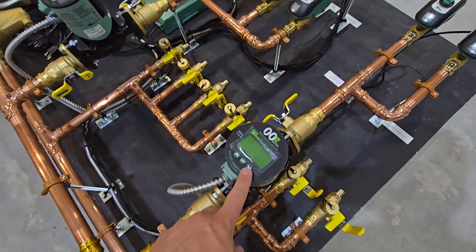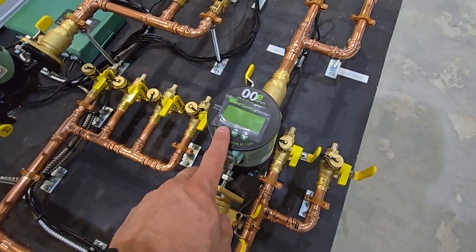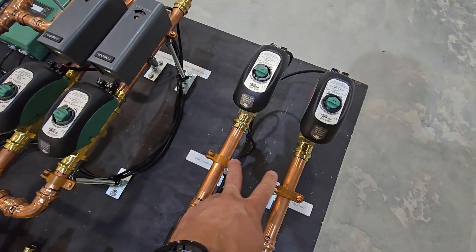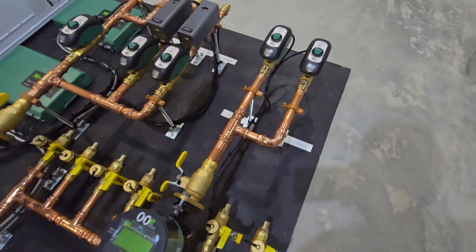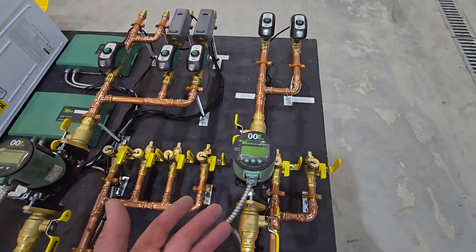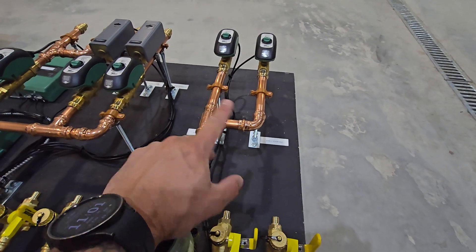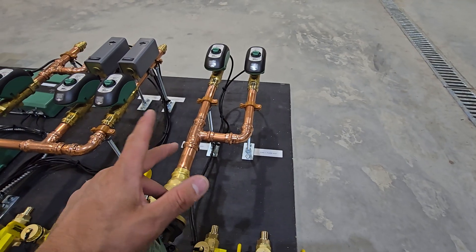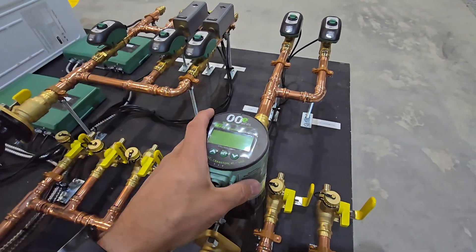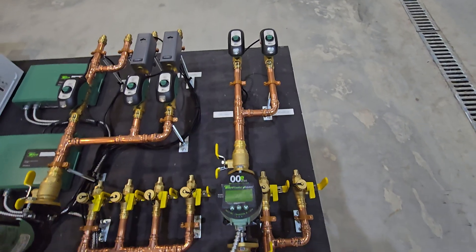You can see there's a single variable speed circulator — a Taco 00e series, specifically the VT 2218 variable speed delta T circ — and that's feeding two zone valves that split to two manifolds. You might wonder why there's a single circulator feeding two zones. These radiant zones one and two are feeding very small manifolds: one has only two loops and the other has four, so this circulator is more than enough to handle both zones.